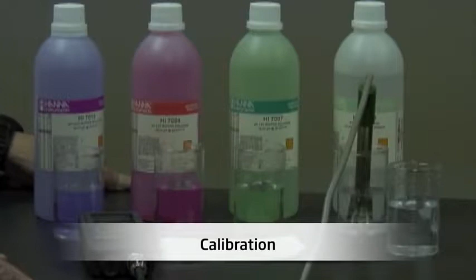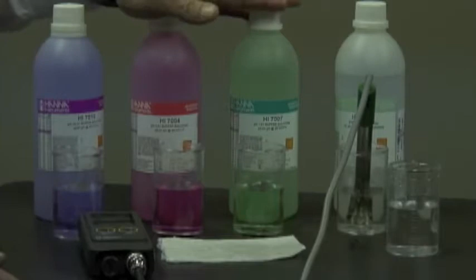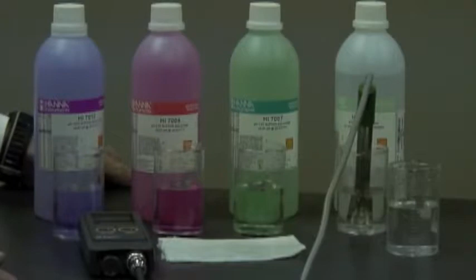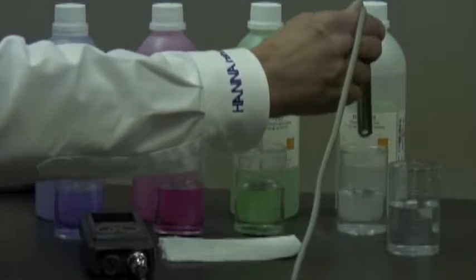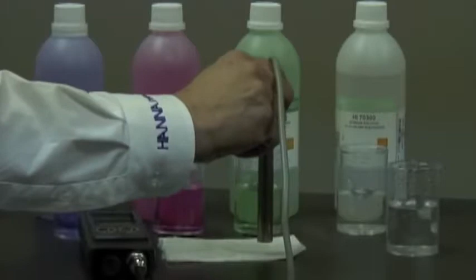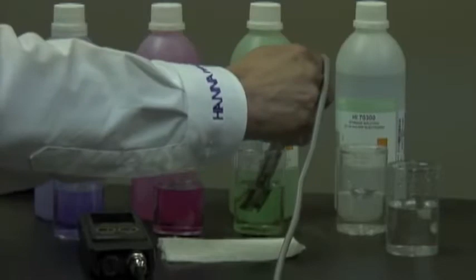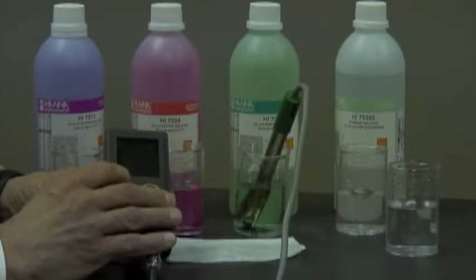Before I calibrate my pH probe, it's very important to condition it first. So what I've done is I've taken the liberty of putting the probe in a storage solution. In this case, it's HI70300. Now, if you don't have a storage solution handy, that's okay. It's fine to use a buffer solution as well. I'm going to let the probe rest in the storage solution for approximately 2 hours. After 2 hours, I'm going to take the probe out, rinse it off in purified water, and just blot it lightly on a paper towel so it dries. I'm going to go ahead and put it in buffer 7.01, turn my meter on, and let it go into its measurement mode.